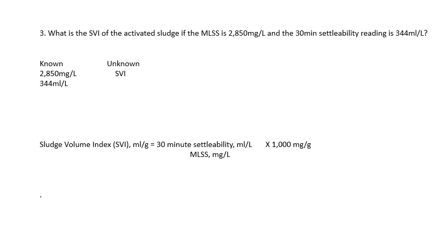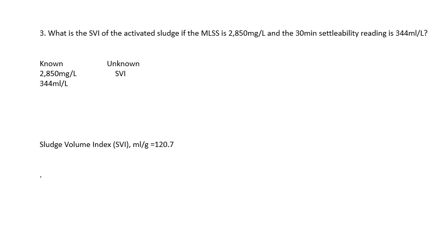The formula for Sludge Volume Index is still 30-minute settleability divided by the MLSS times 1000 milligrams per gram. Plugging our numbers in: 344 milliliters per liter divided by 2850 milligrams per liter, times 1000 milligrams per gram. Everything will cancel out and your answer is 120.7 milliliters per gram.